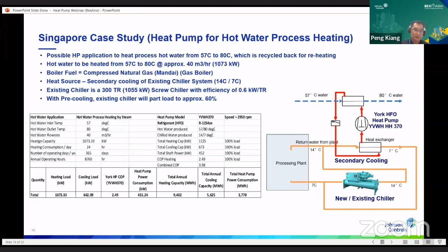So based on this and the selection of the heat pump in this case, we can use our standard product for HFO heat pump, a high temperature heat pump, to generate hot water up to 80 degrees and cool water down to 7 degrees. And again, we are doing the same kind of parallel study between using a boiler with natural gas, with the current Singapore rate of about 0.3247 Singapore dollars per kilowatt-hour for electricity, and the boiler fuel at about 2.4 Singapore dollars per kilogram of natural gas.